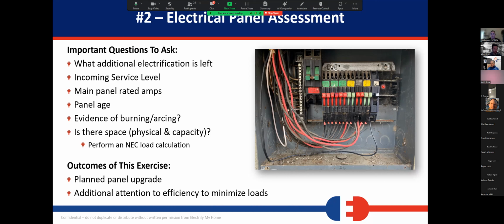We did a job recently with a Stab-Lok panel that was not at capacity. They're going to put in solar and battery in 6 months, so they'll get a new panel then, but we were able to drop our heat pump into the existing panel and leave enough wire under the house for them to pull new wire up into the new panel later. We got those people heat before the end, just by knowing there was capacity available on their old Stab-Lok panel.